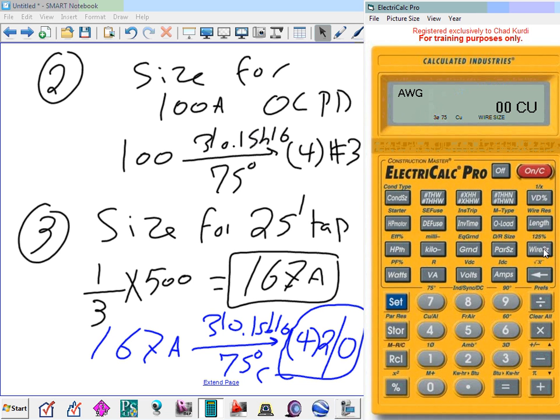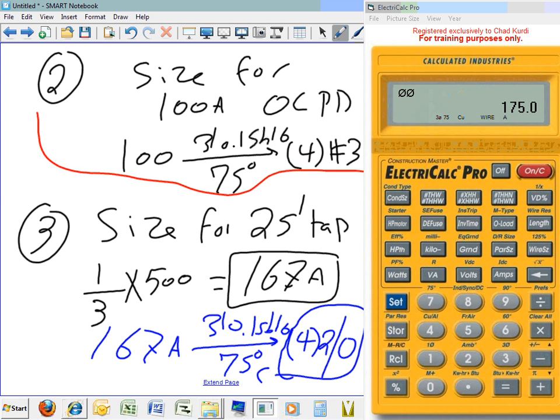The last thing, guys, is find the overcurrent device. You have to land this conductor on an overcurrent device. So I think if you hit twice, it gets you the amp of 2 aught. Yeah, if you hit it twice, it gives you the amp. So my amp is 175, right? Is that the amp for 175 for this conductor? 2 aught is 175. Now I have to land this, I'm going to size the overcurrent device for this. So let me, how am I going to say that? I'm going to do it right in here so it will be all the same. Size overcurrent protection. Well, let's do it in the second one.